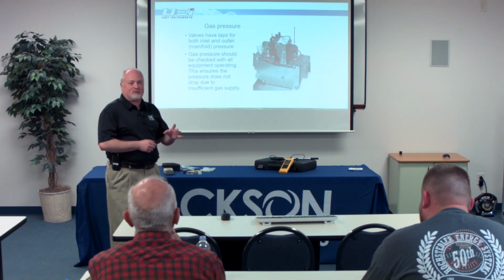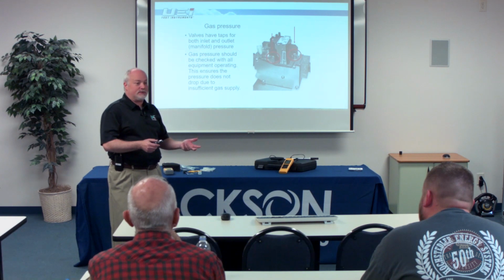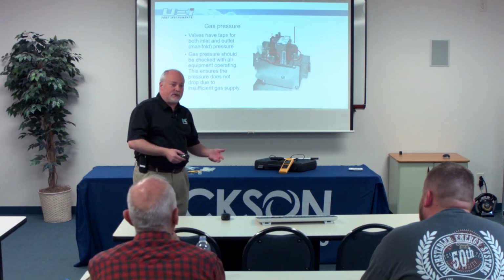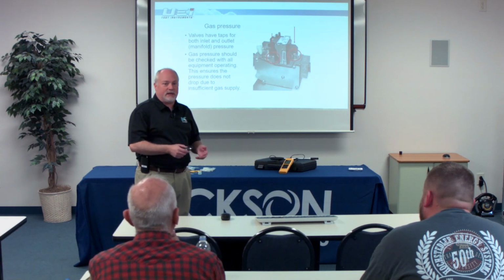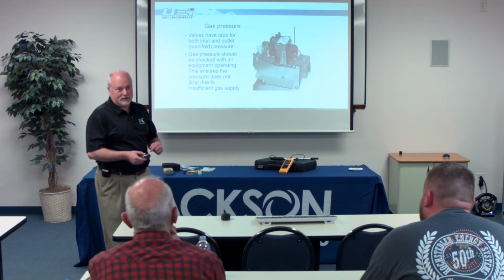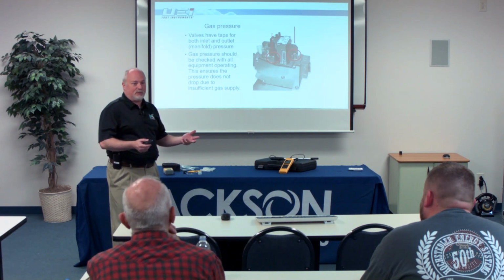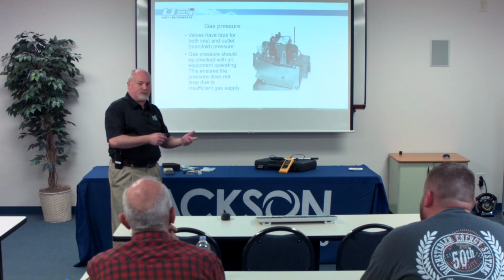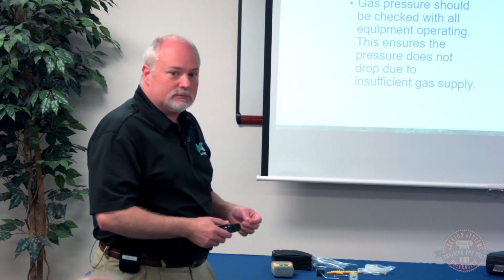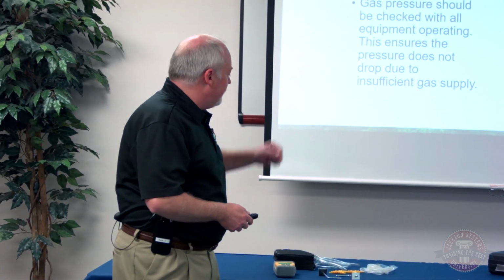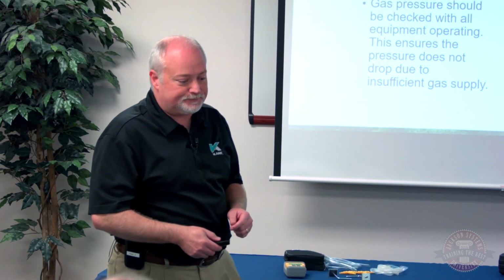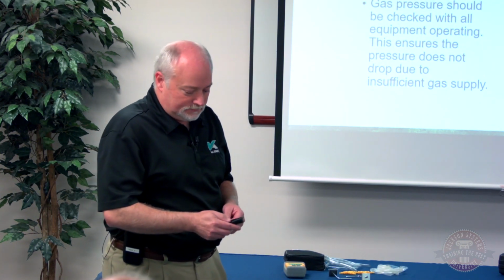So somebody had replaced the gas regulator, and rather than getting the appropriate sized one, they just used what they had on the truck. So he had a regulator that had about 50,000 BTU capacity and two 100,000 BTU heaters on that gas line. So what was happening was, as soon as the equipment came on, the gas regulator couldn't supply enough gas volume, which of course dropped the pressure. So anytime you're doing gas pressure, make sure the equipment's operating so that we're not having an issue with insufficient supply. Okay? Any questions at all on gas pressure before we move on to some of the other things that we can do with our manometer? No. Okay. All right.